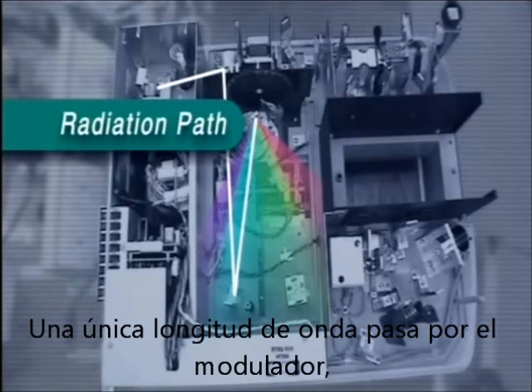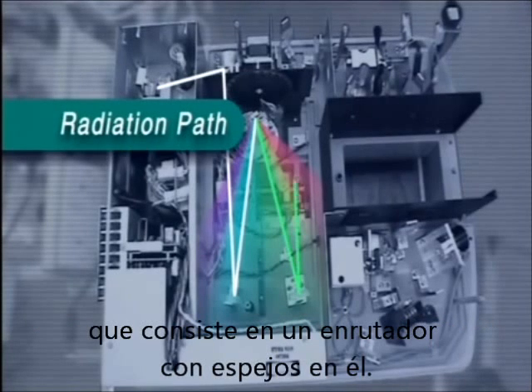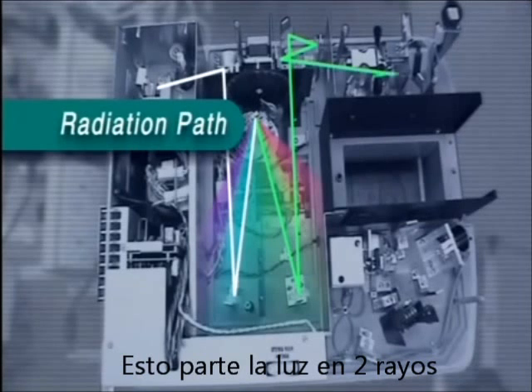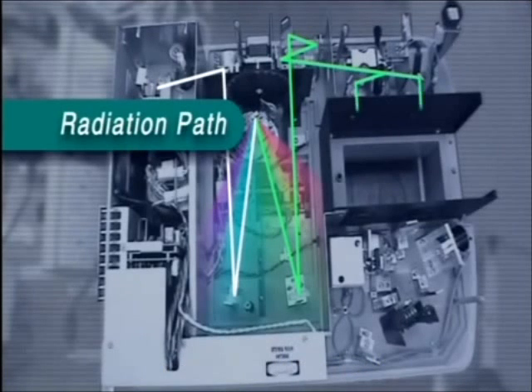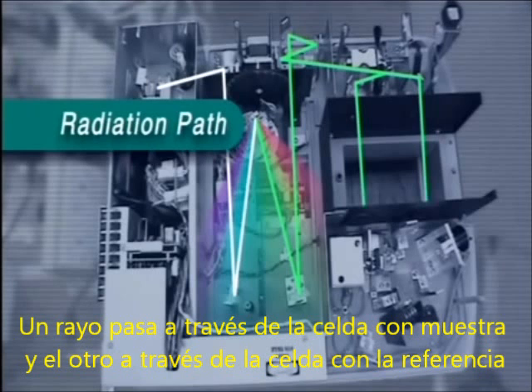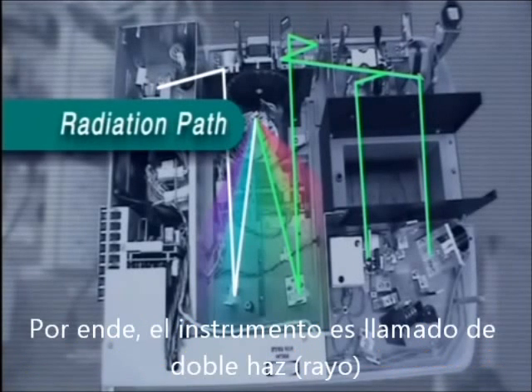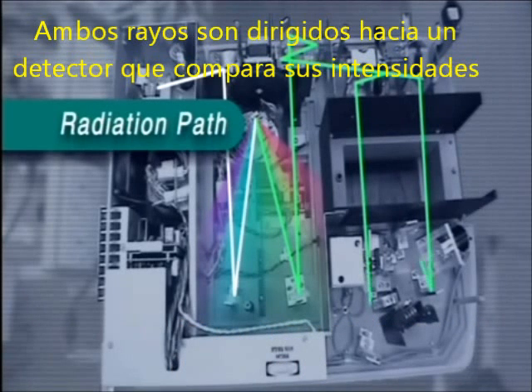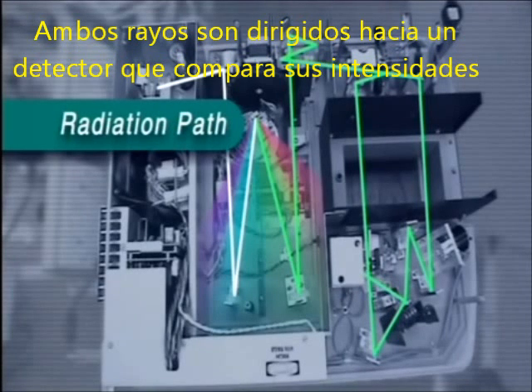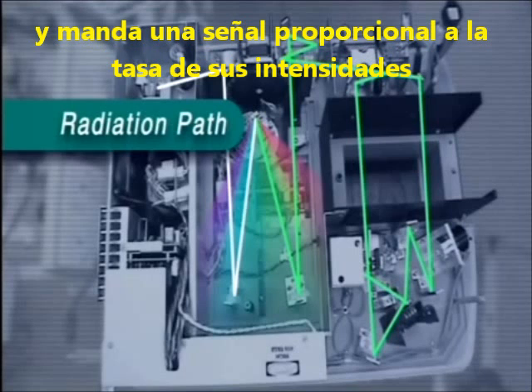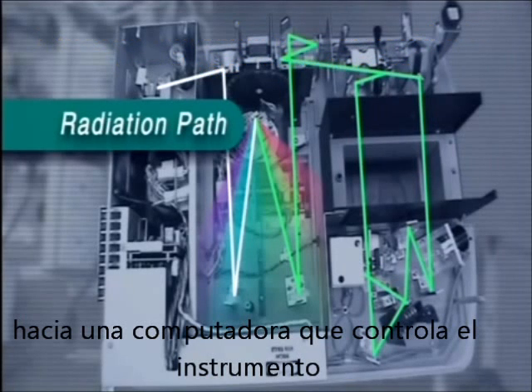A single wavelength passes into the modulator, which consists of a rotor with mirrors on it. This chops the light into two beams. One beam passes through the sample cell, while the other passes through the reference cell, so the instrument is referred to as a double-beam instrument. Both sample and reference beams are directed by mirrors onto a detector, which compares their intensities and sends a signal proportional to the ratio of their intensities to the computer that controls the instrument.